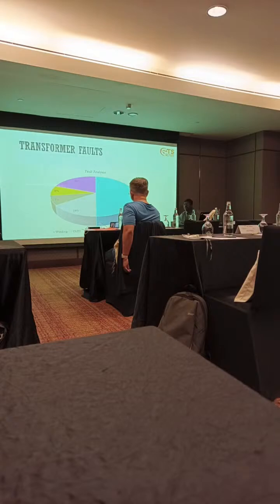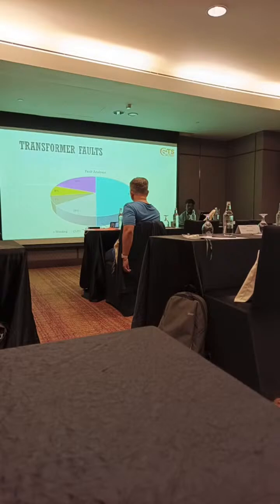What could be the affected components? Let's say we are looking at the components of the transformer. If a fault happened and the transformer failed, the most commonly affected component is the winding, the first one. The second one is 20%, which is miscellaneous or unknown reasons. Then 15% is the OLTC; since it has moving parts, the failure rate of the OLTC is higher. Another one is the bushing and the insulation. These are the common failure rates of transformer components. And why it is failing, the reasons we have shown before.